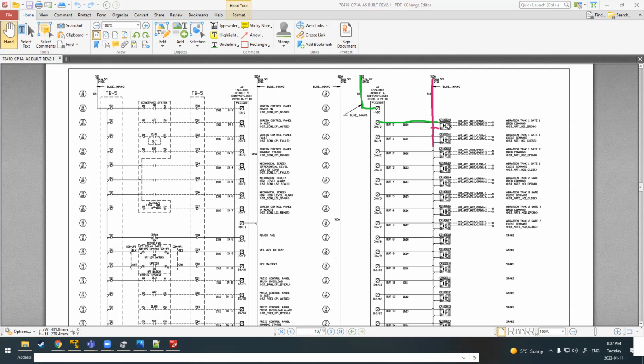Likely these are called interposing relays. They're used when you need to switch voltages. So this is probably 120 volts, even though it's not listed here. 24 volt relays with 120 volt contacts.